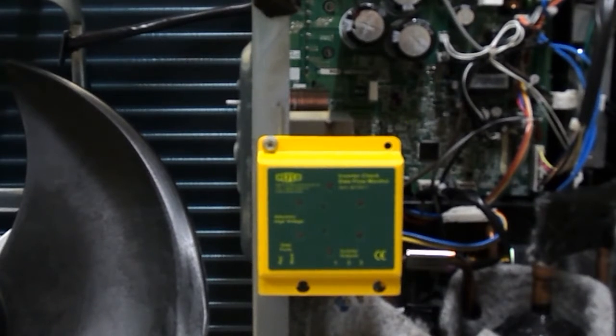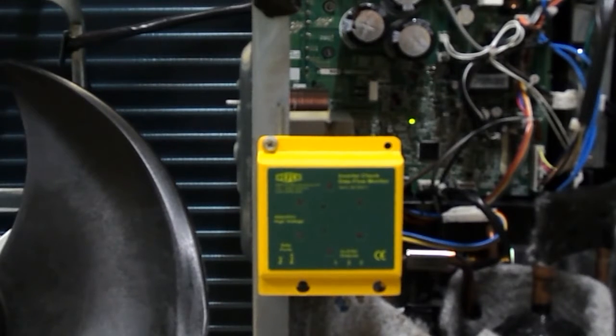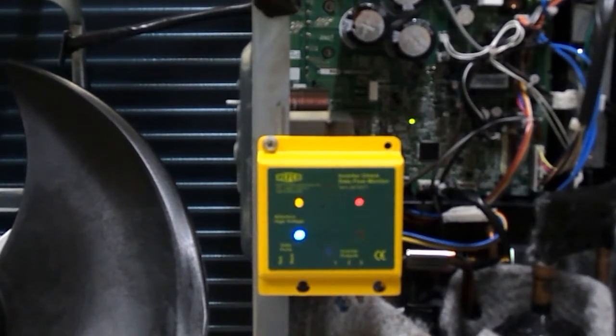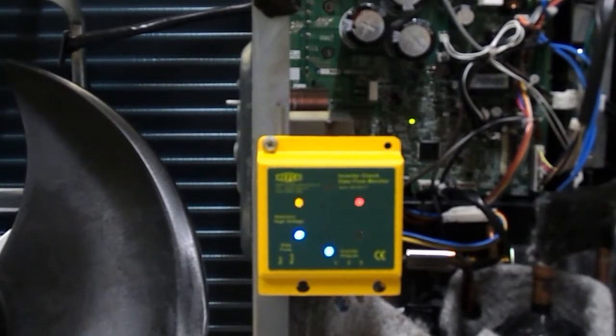Now, when you do this test, you're actually replacing this device for the three-phase UVW going into the compressor. When it operates, the unit itself, as you can see now, will be showing a series of six lights flashing.